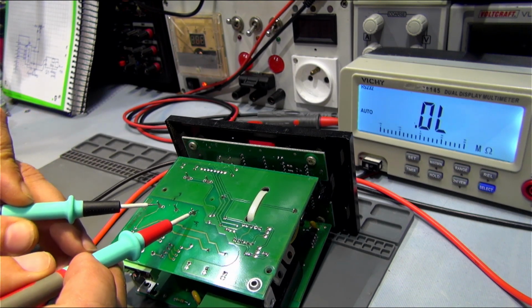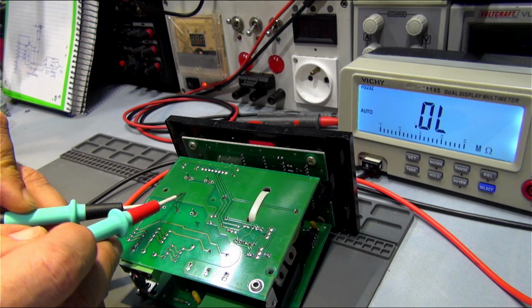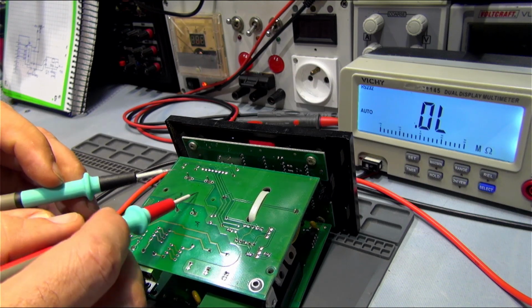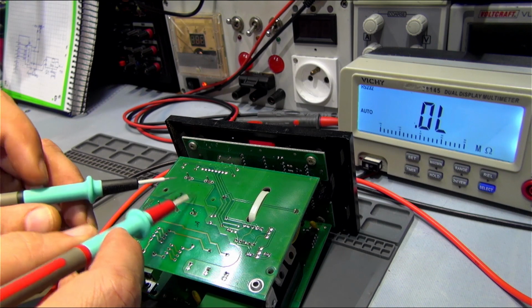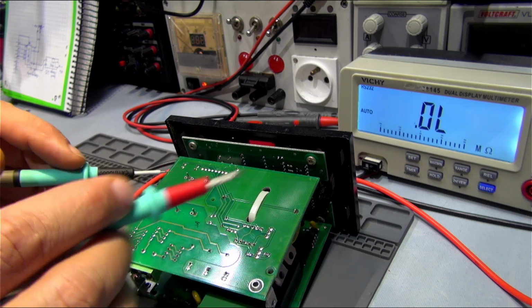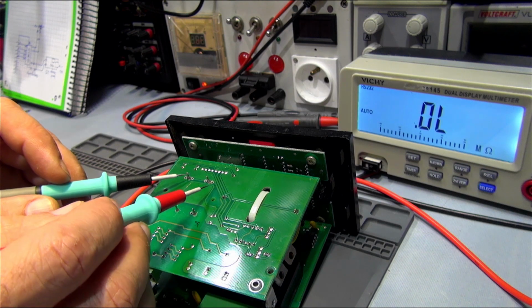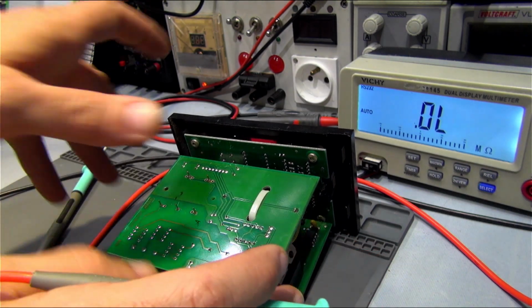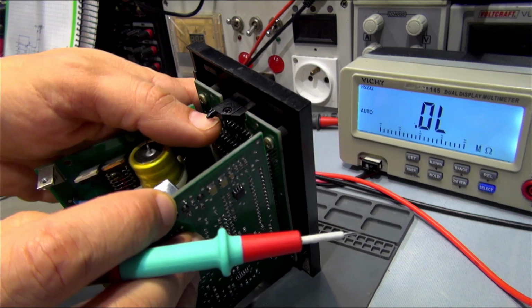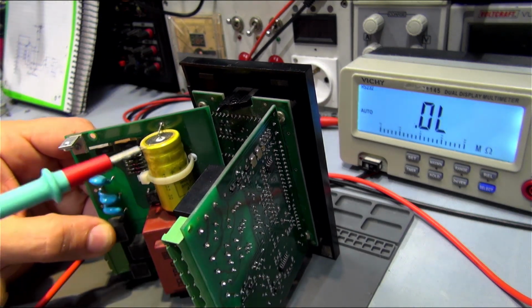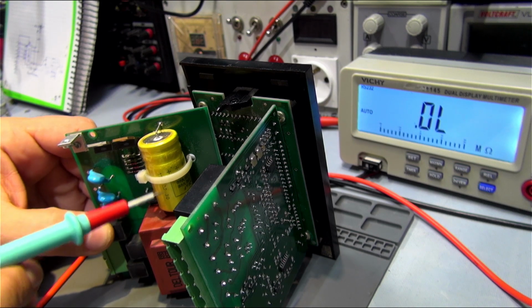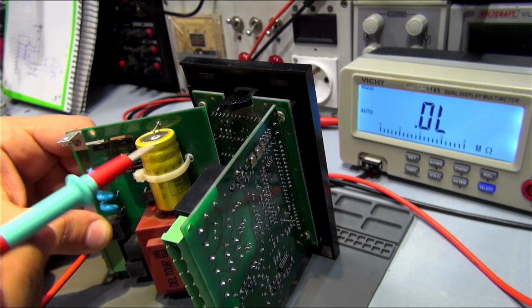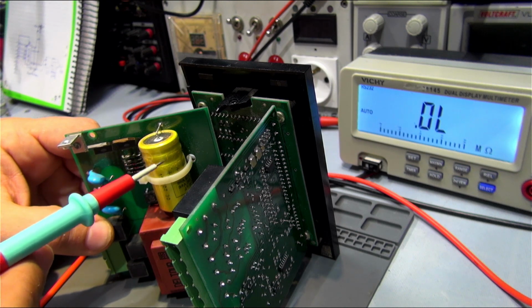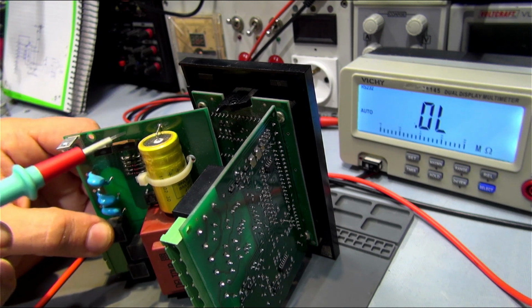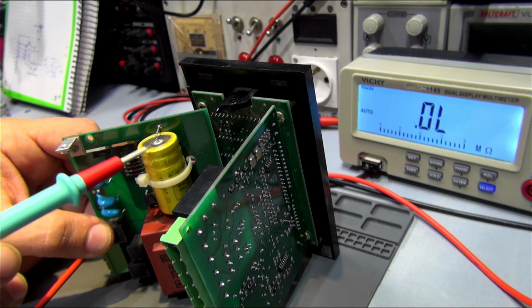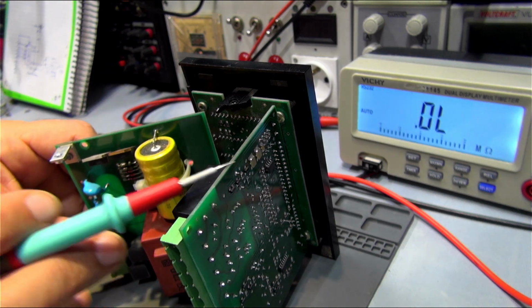So this primary here is disrupted. We don't know if the coil is broken or if there's a fuse inside. We absolutely don't know. But the main thing you need to know is whether the rest of this device is still working. To check that, you simply inject some voltage matching what's shown on the capacitors. I'm not going to play with high voltage here, I'm just going to inject something like 50 volts and see if the device reacts.